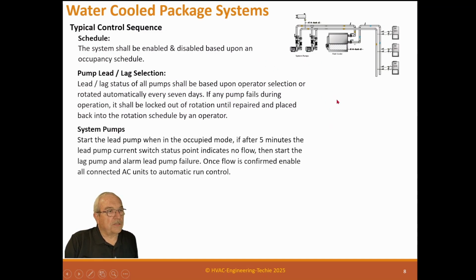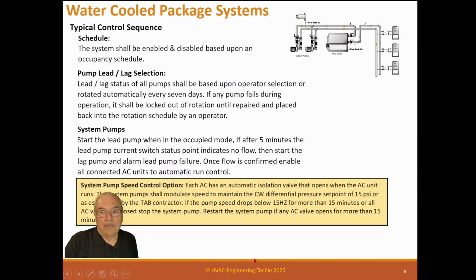System pumps. These are the system pumps. Start the lead pump when in the occupied mode. If after 5 minutes the lead pump current switch status point indicates no flow, then start the lag pump and alarm pump failure. Once flow is confirmed, enable all connected AC units to automatic run control. Now, you can run variable speed pumps like I mentioned, and this is that each AC unit has an automatic isolation valve that opens when the AC unit runs. The system pump shall modulate speed to maintain the condenser water differential pressure set point of 15 psi, or whatever is established by the TAB contractor.